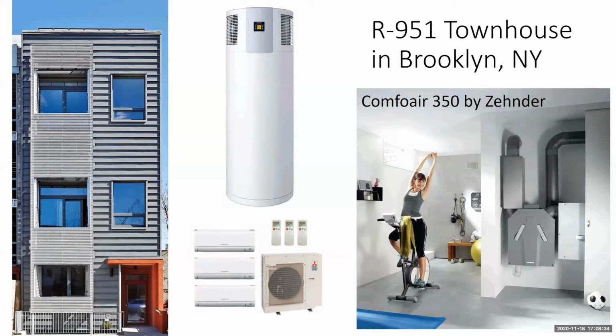I wanted to point this out right away: in really cold climates, the cheap way of doing it is to use a heat pump water heater inside the envelope. It doesn't need fresh air, just needs heat. These use R134A refrigerant, which generally doesn't work below freezing, so it wants to be inside a warm envelope. In warmer climates, like California, they're used year-round with outside air. But once you get into cold climates, you should bring it inside the envelope and heat the air with a specialized cold climate HVAC heat pump, like what you're seeing below. That's the inexpensive, totally reasonable way of doing it. It'll chill a room about 1 degree over the course of a day.